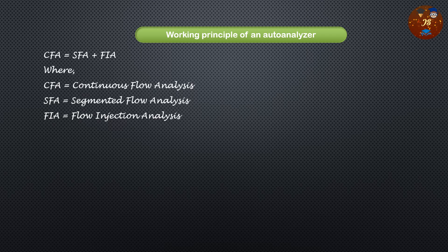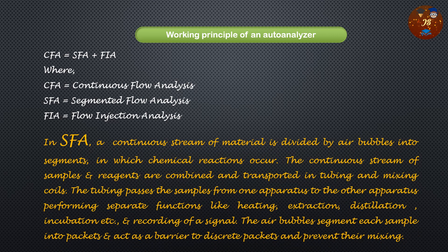Regarding the working principle: CFA = SFA + FIA, where CFA is continuous flow analysis, SFA is segmented flow analysis, and FIA is flow injection analysis. In SFA, a continuous stream of material is divided by air bubbles into segments in which chemical reactions occur — for example, a drop of blood is segmented into small parts, and each part is analyzed separately for a different outcome.